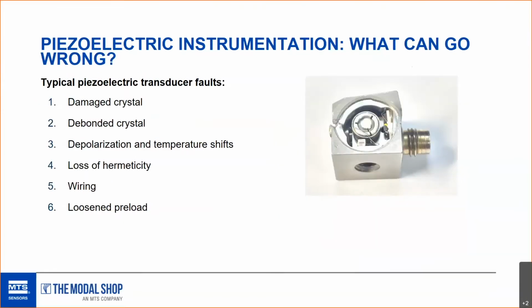So the question might be, what can go wrong with my piezoelectric sensor, Mike? Well, some of the ways that piezoelectric transducers fail are due to damaged crystals or debonded crystals or depolarization. Most industrial instrumentation has a ceramic sensing element, which is not naturally piezoelectric. So it's artificially polarized. And over the course of time, the depolarization of the sensing element can cause sensitivity shift. You can also have a loss of hermeticity or broken wiring or a loosened preload. And I'd like to point out that on gas turbine sensors, all of them are high temp charge mode sensors. So they don't have a bias voltage.